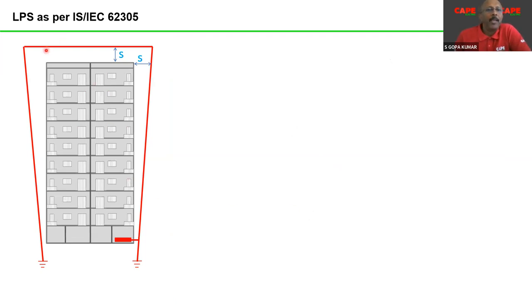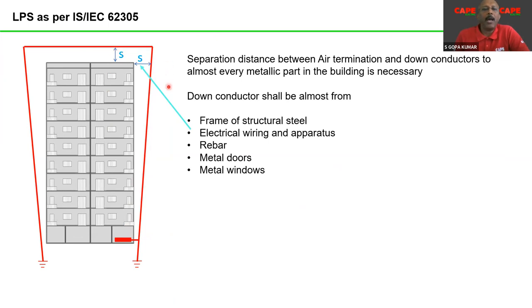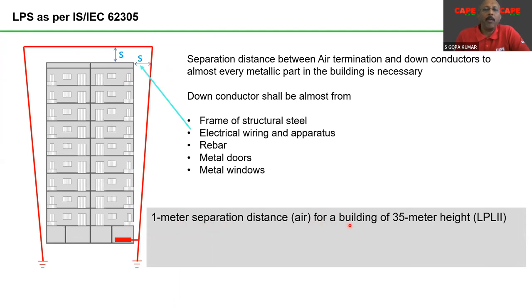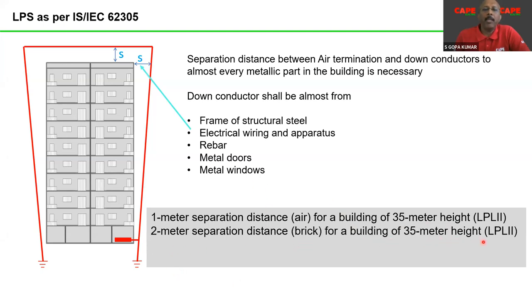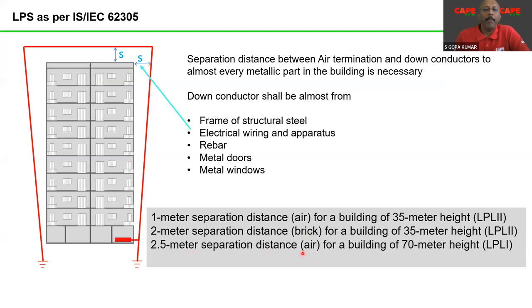What does this mean? The air termination mesh and the rod and parts of this down conductor, see, at the bottom you have equipotential bonding. Away from the equipotential bonding, the distance increases, and at the roof of the building a distance of certain meters is required between the air termination, or between the parts of the lightning protection system, and the building material. How far is it? 1 meter separation distance for a building with a 35 meter height, level 2, as in the previous case which I explained. 2 meters if the insulation material is actually brick, not air. 2.5 meters in air if your building is 70 meters high. 5 meters if your building is 70 meters high and the insulating material is brick.